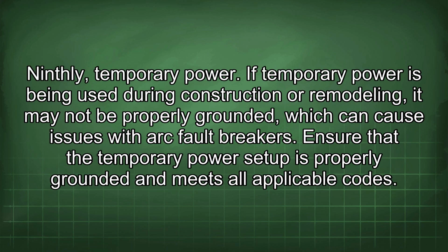Ninthly, temporary power. If temporary power is being used during construction or remodeling, it may not be properly grounded, which can cause issues with arc fault breakers. Ensure that the temporary power setup is properly grounded and meets all applicable codes.